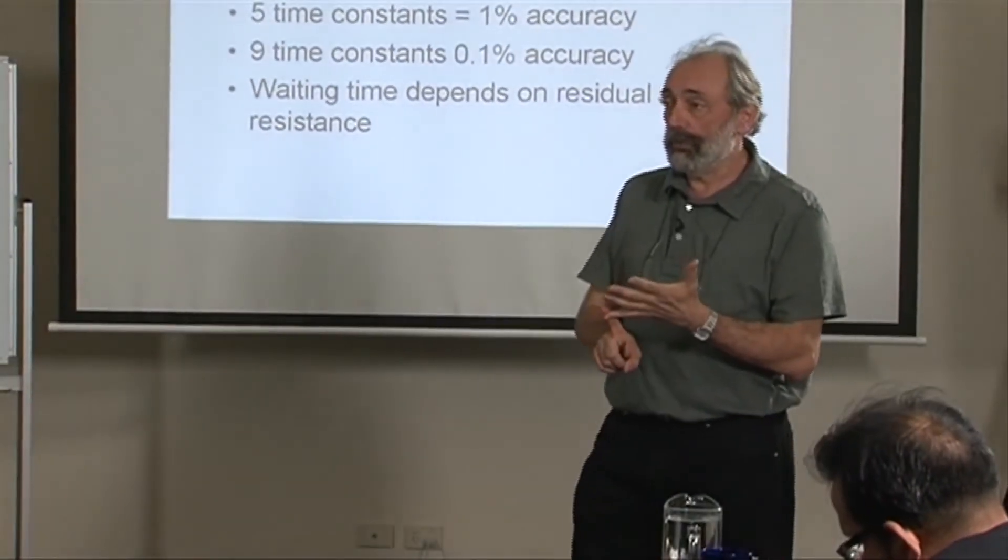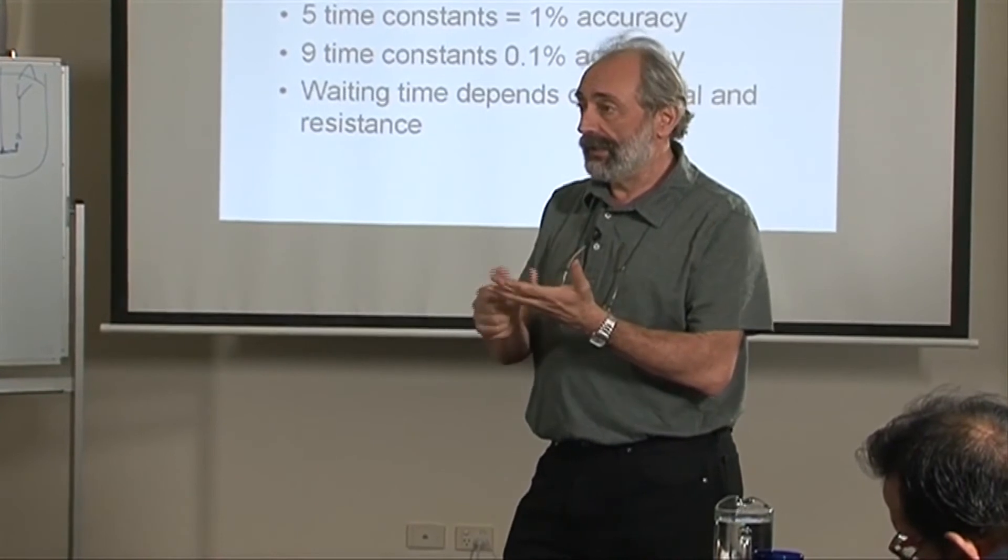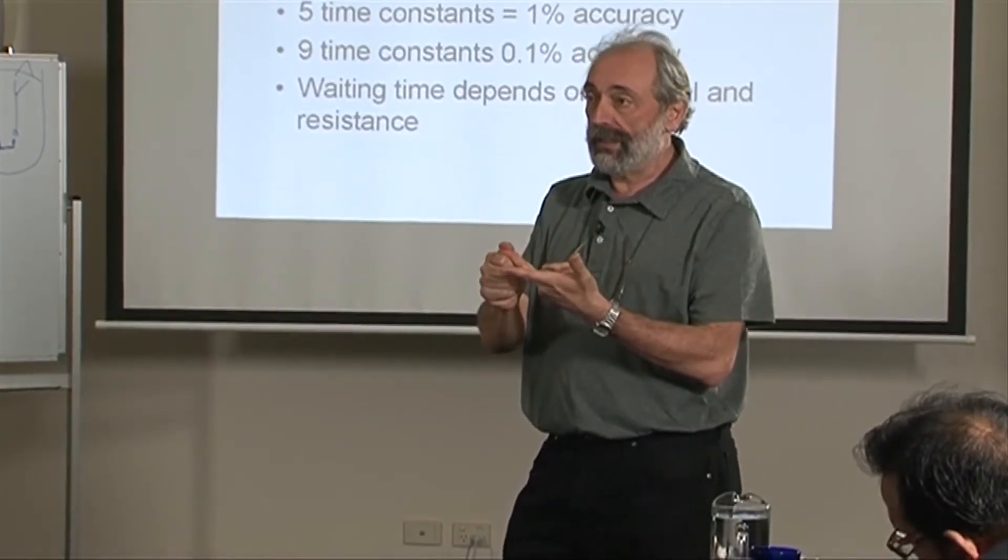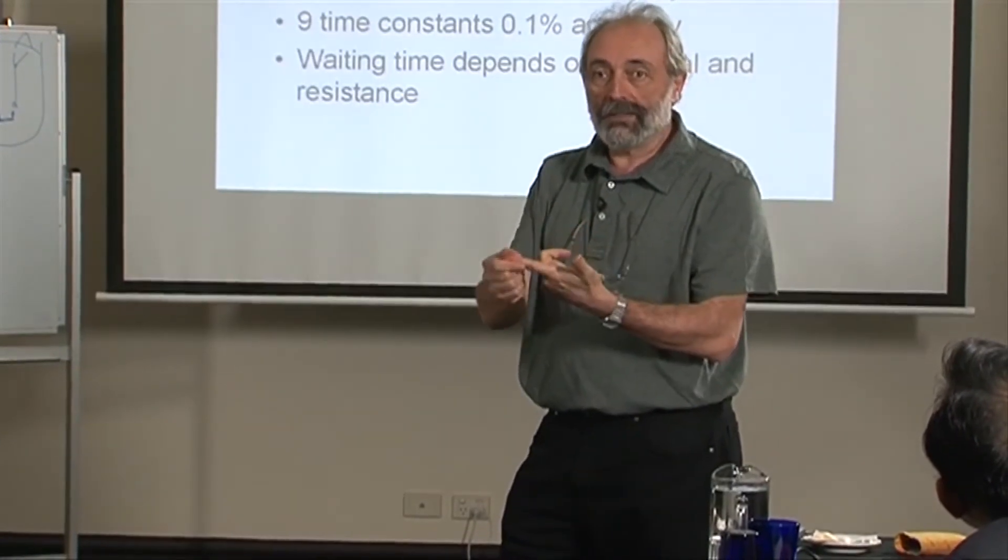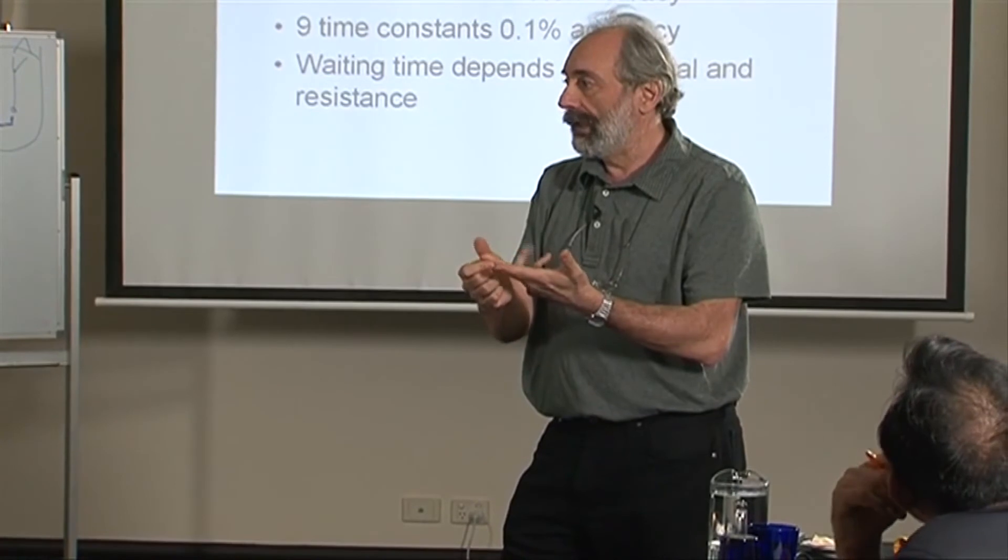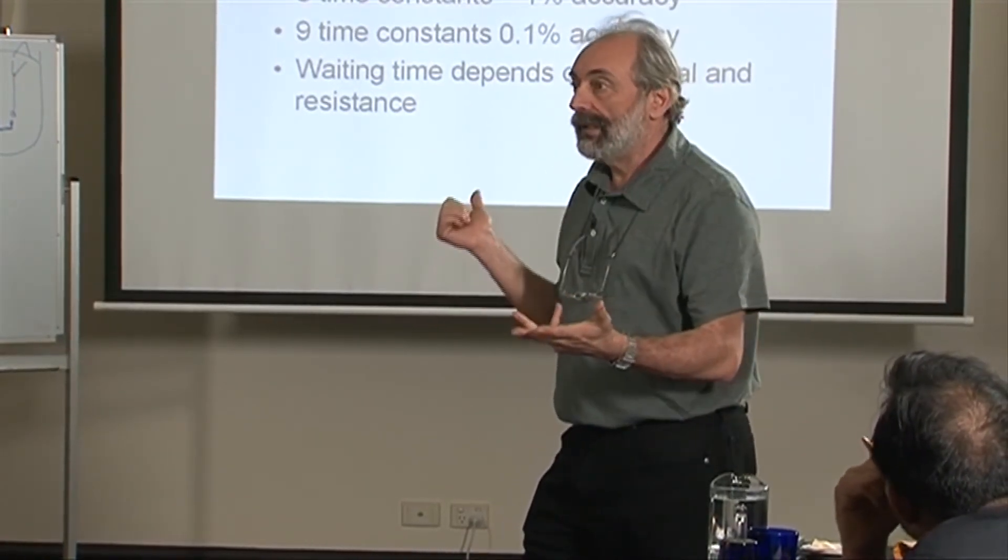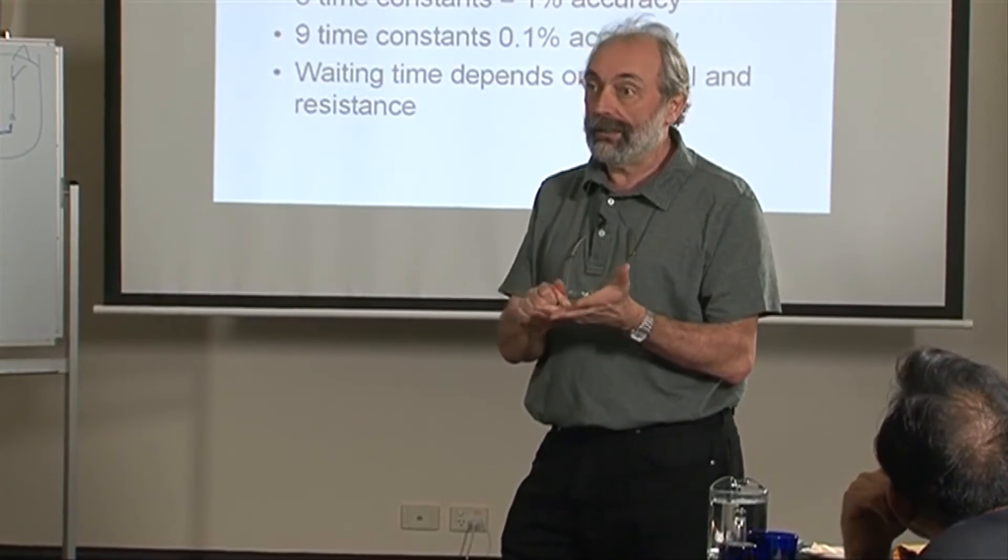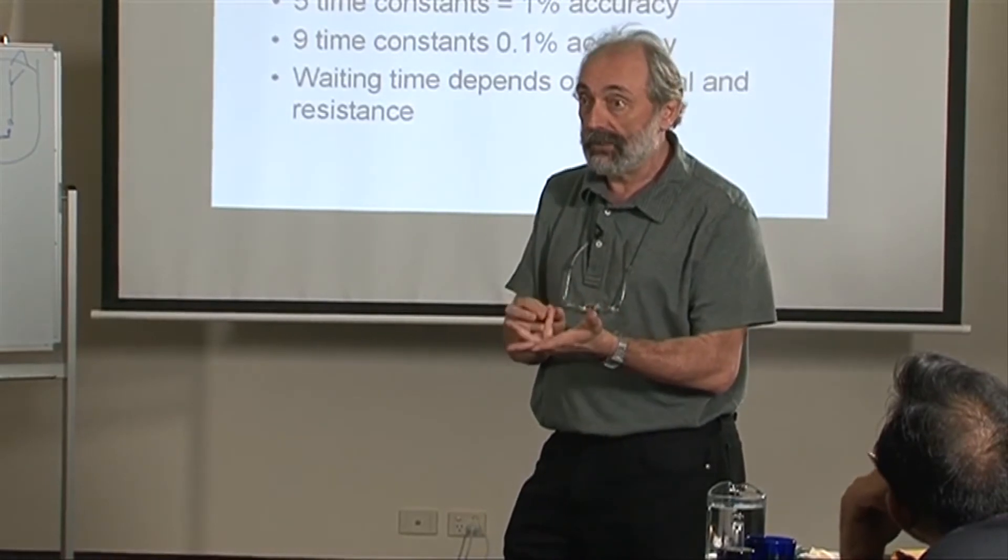You do a test on a transformer. You start in the morning. You probably do tangent delta, bushings, excitation, turns ratio, SFRA, polarization index, short circuit impedance. I don't know what else you do. And by the time you come to this particular test, which is always the last one, the DC test, you always do last.